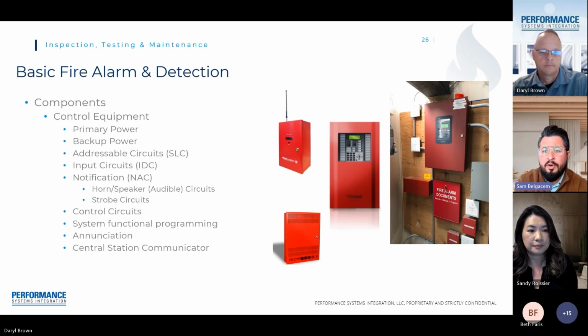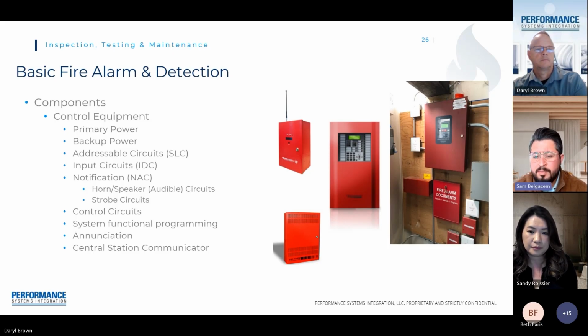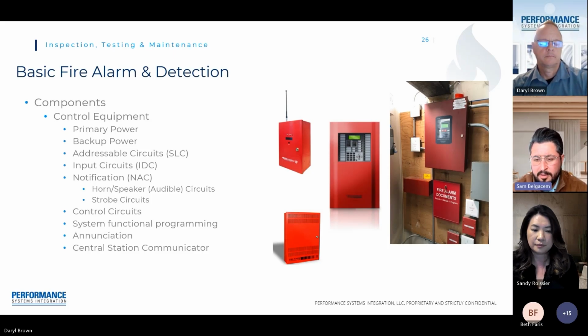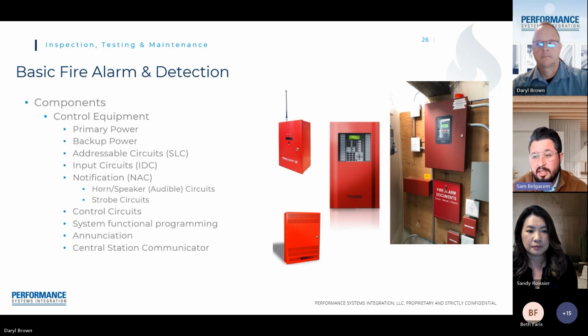The main component of the fire alarm system is the control panel, which is powered by the primary power supply. And by law, it is required to have a backup battery in case we lose power. The backup battery will trigger and will ensure that the system keeps functioning. The control panel is connected to 2 types of devices. There is a detection device that detects fire, and then there is a notification device that alerts the tenant in case of fire. It's also connected to the communicator, which is connected with the central station.